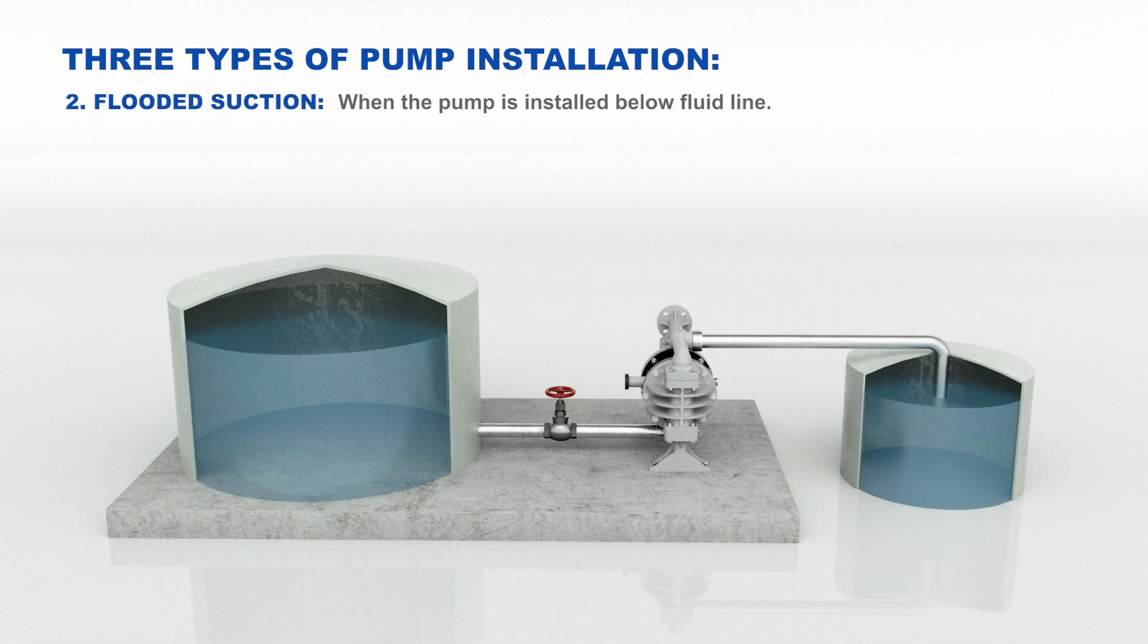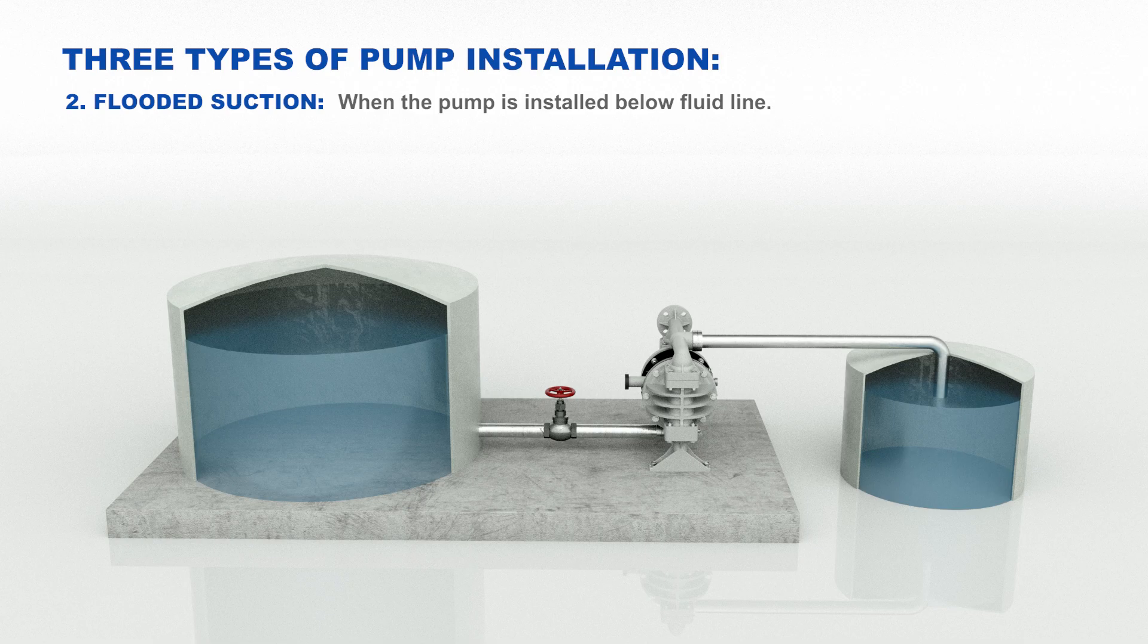Flooded suction. When the pump is installed below fluid line, ensure there is a valve installed between the pump inlet and the tank to protect the pump from inlet fluid pressure exceeding 10 PSIG.